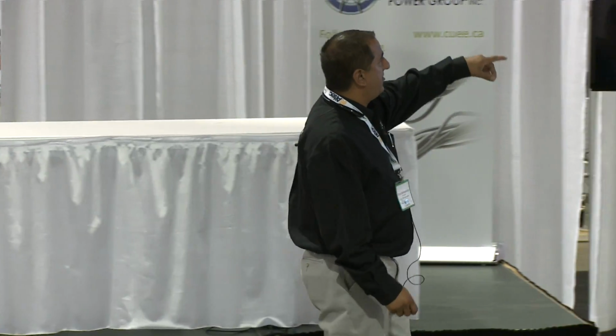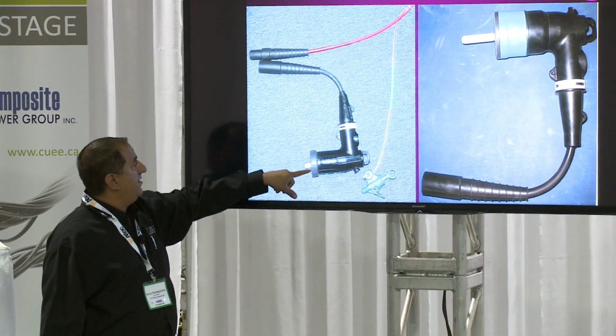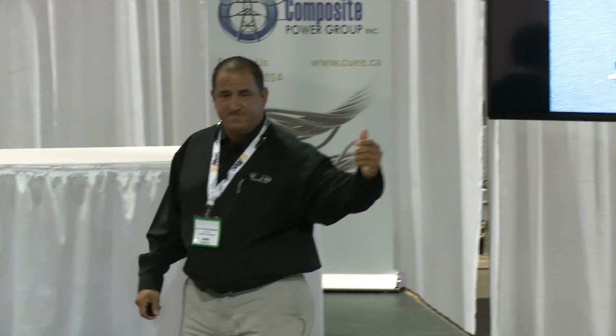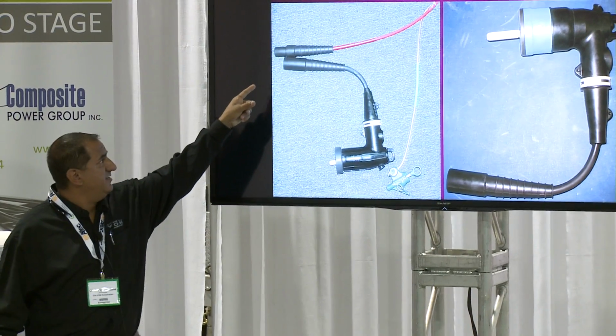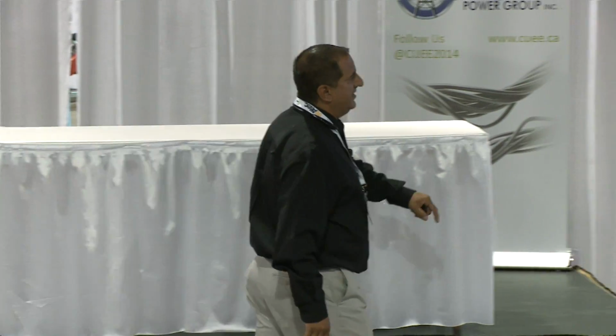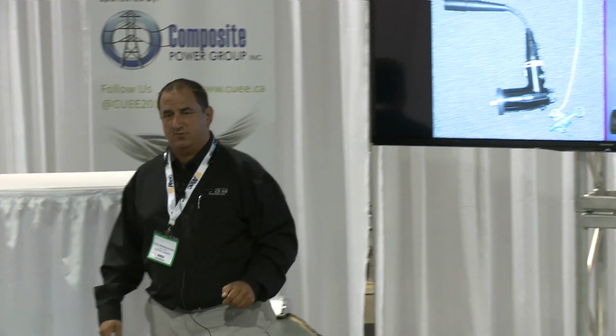When you're hooking up our equipment, you've got 3 connections that we're going to make. You can use a load break elbow. That's going to plug right into our high voltage lead, and that's going to go right on the conductor that we're going to test. This green cable right there is going to go on the neutral. The importance of that connection is that it goes on the neutral of the cable that we're going to test. That's going to be our return path to the machine. When you're analyzing your cable, you send a pulse down that center conductor. It's going to look for an impedance change, and it's going to come back to the machine, and it's going to travel on the neutral. So as long as our neutral is intact and we have a good neutral, we're going to be able to get that accurate distance.